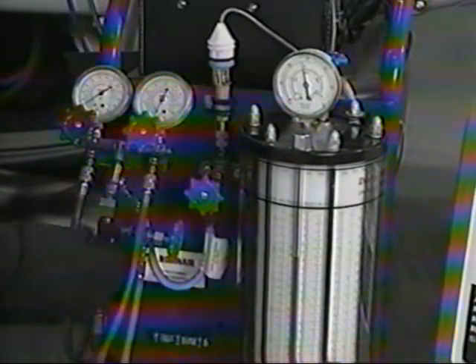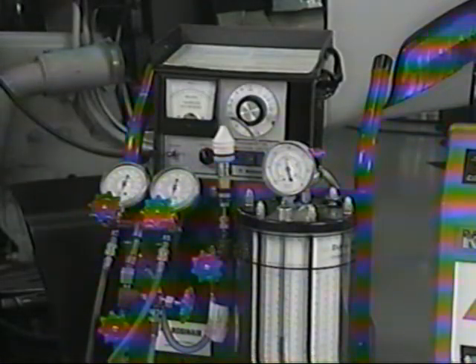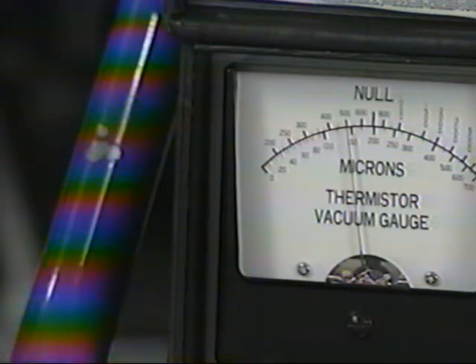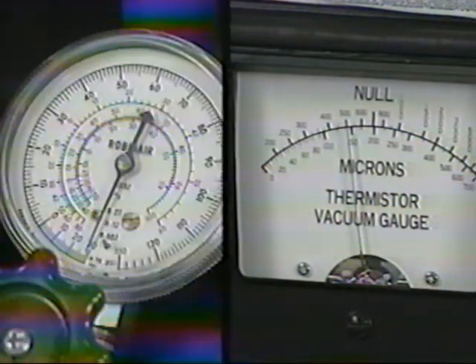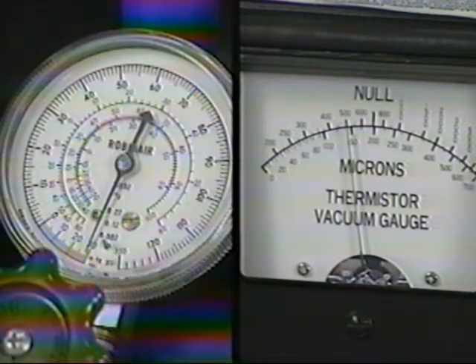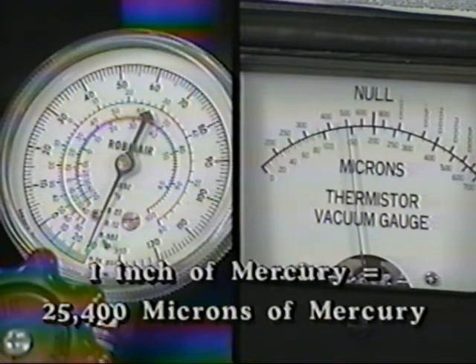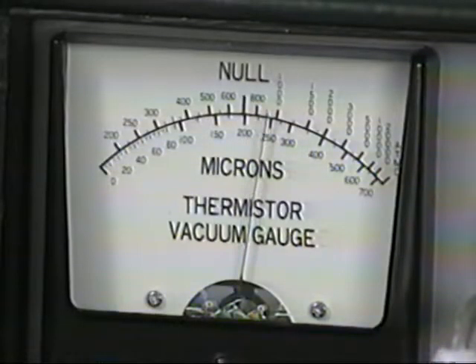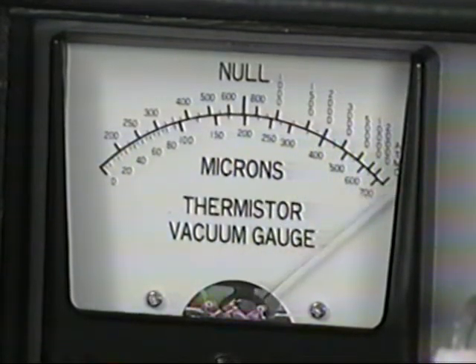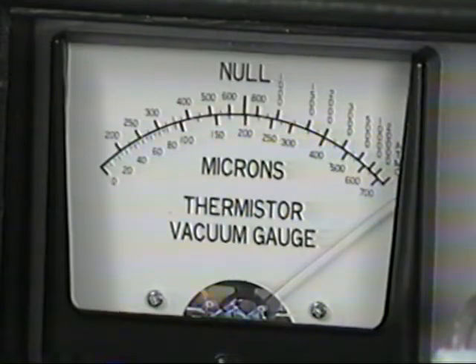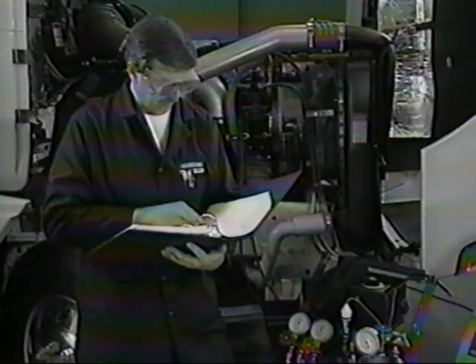Before the system is charged, it must be evacuated to remove any water vapor. This is accomplished by lowering the system pressure using a vacuum pump, causing the moisture to vaporize at ambient temperatures. Check the service manual for detailed evacuation instructions. To be certain the system doesn't leak or contain any moisture, connect a thermistor gauge. This gauge measures the vacuum in the system in microns of mercury compared to inches of mercury, as indicated on the charging station's gauges. 1 inch of mercury equals 25,400 microns of mercury, obviously a much finer and more accurate method of measurement. If there is any moisture in the system, the pressure will rise. Continue to evacuate the system. If there's a system leak, the pressure will soar. Repair the leak. You're now ready to charge the system with new refrigerant.